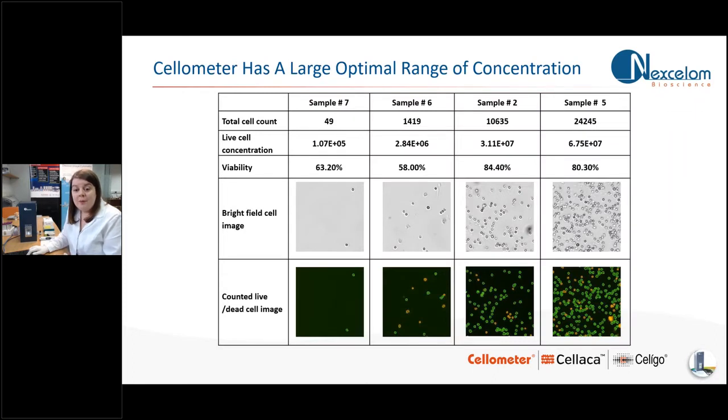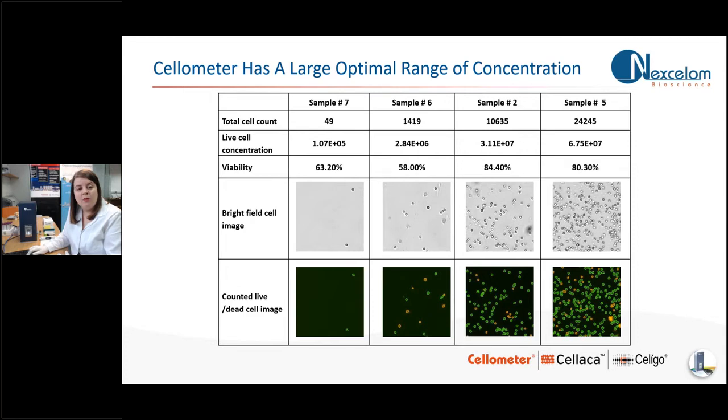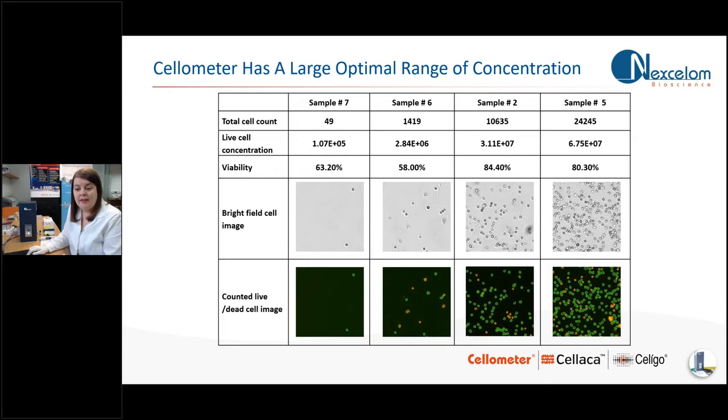Just a few technical points before I show you the live demonstration of the Spectrum. In terms of concentration, the Spectrum will give you accurate results for cells between 1 times 10 to the 5 and 1 times 10 to the 7 cells per ml. But if tested, you can also extend that range beyond 1 times 10 to the 7 such as in sample 5 here.